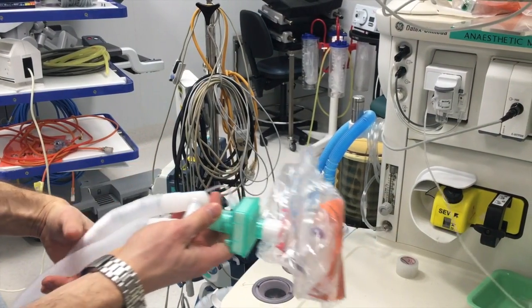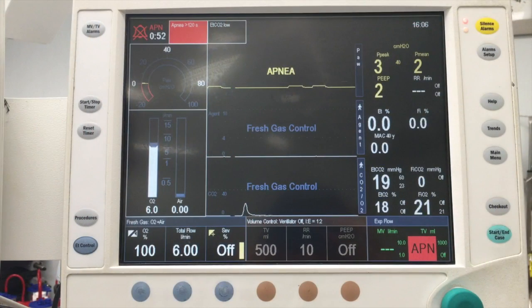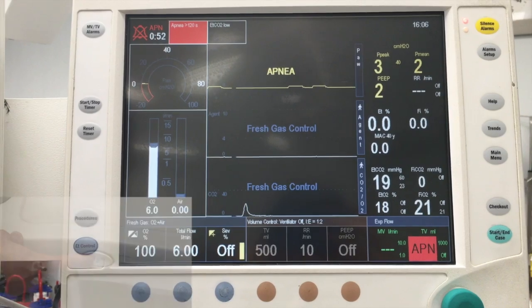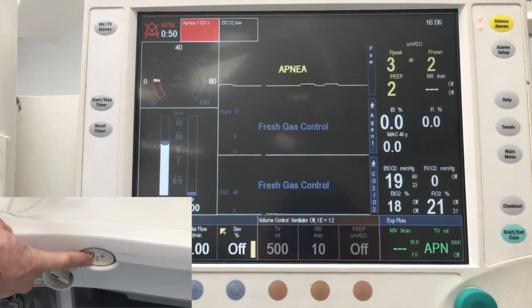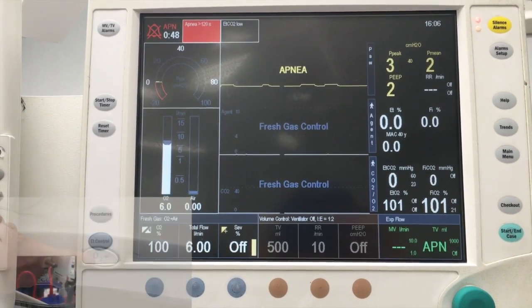Now test the oxygen analyzer. Note on the bottom right hand corner of the screen that the FiO2 is 21%. This is correct for room air, and the oxygen flush button should bring that up to 100.